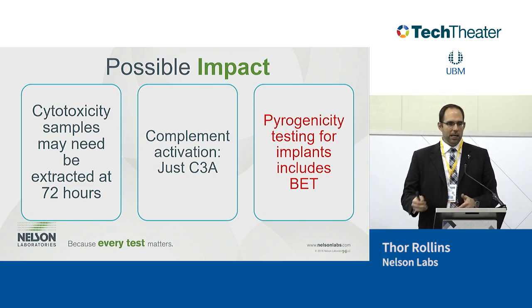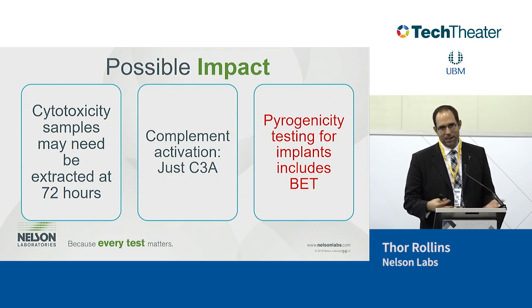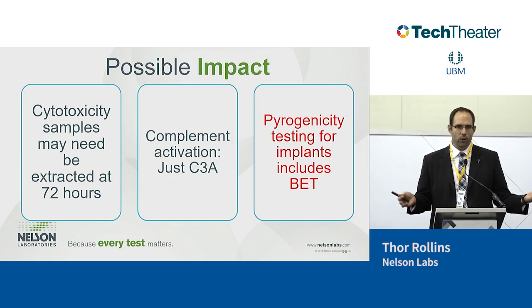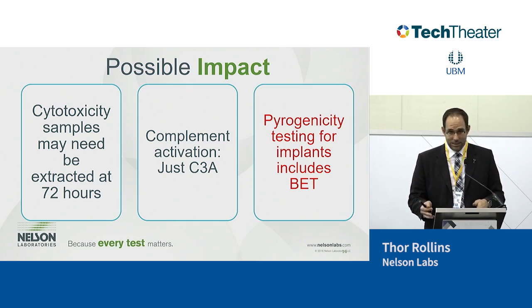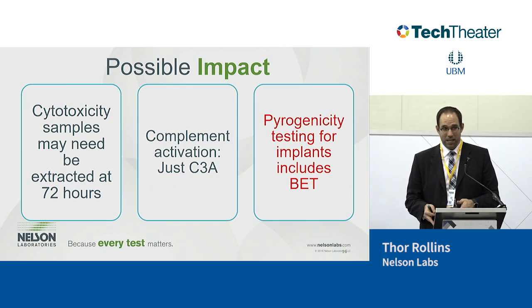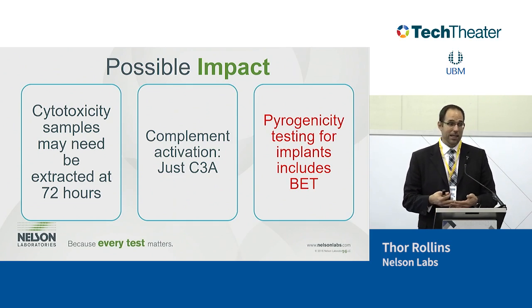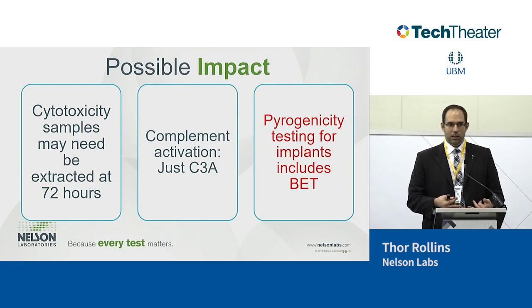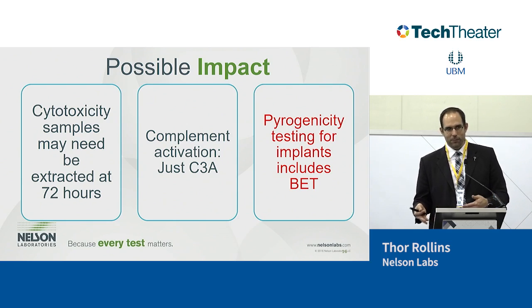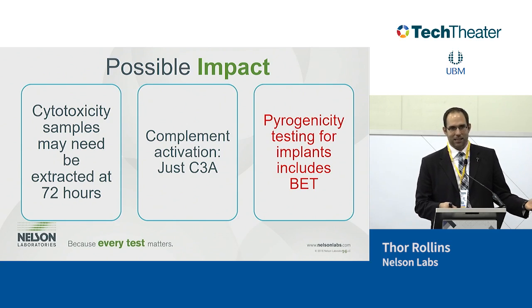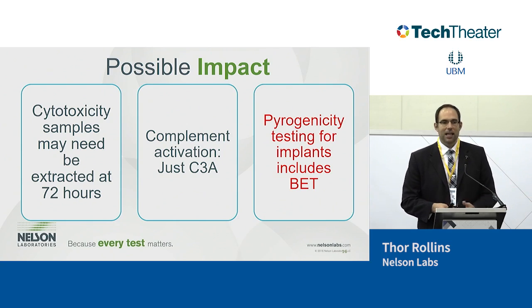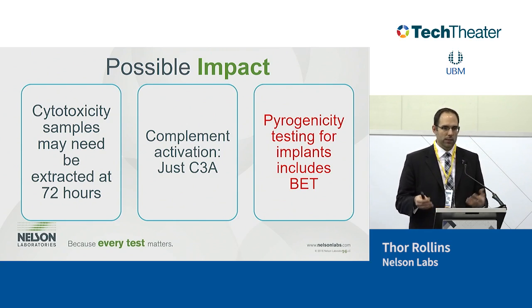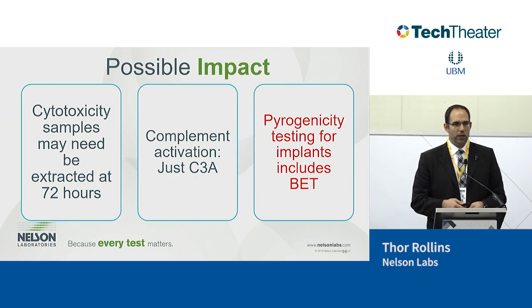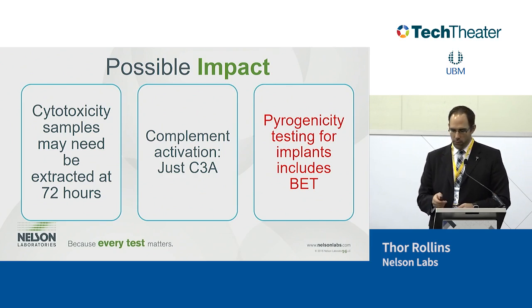Okay? Now, the BET test is not very expensive. It's cheap and quick. At Nelson Labs, it's like $120, and we can do it in 24 hours. But it's the samples that can cost a lot of money. If you're an orthopedic device and you make an implant like a knee, the test isn't expensive, but submitting knees into a test lab for a lot release test can be quite expensive. So it's one of those impactful tests that we're still looking at how the FDA is going to implement going forward.